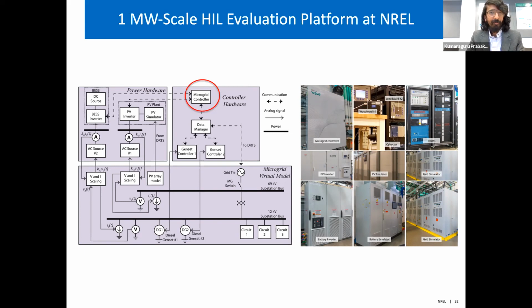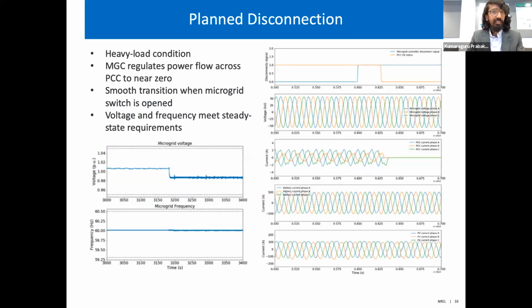I presented a couple of cases in this presentation. The first is a planned plant disconnection, where the utility knows they want to island the system. We ask the microgrid to orchestrate the event: go into island mode, and the microgrid controller decides which asset will be the voltage and frequency master, and which assets will support the P and Q demands of the load. The plots show the event transitioned smoothly. Before we send the command, current is flowing in the PCC circuit breaker, but once the microgrid was islanded, the current went to zero, and the controller maintained voltage and frequency in that mode.